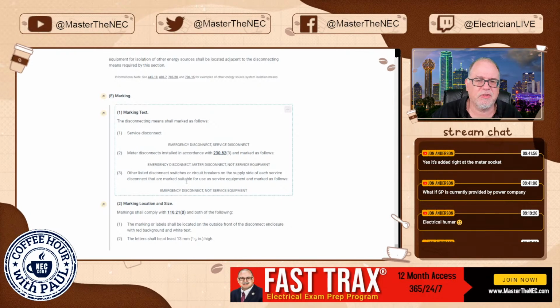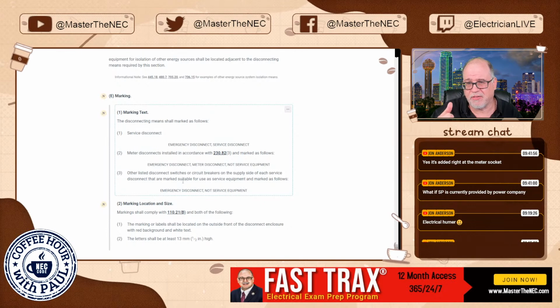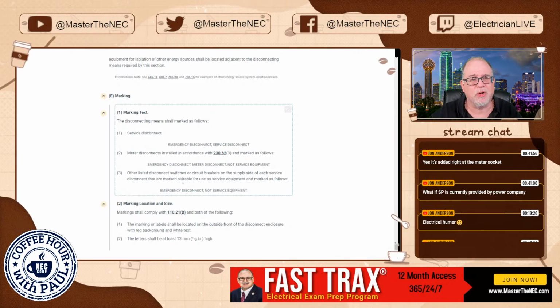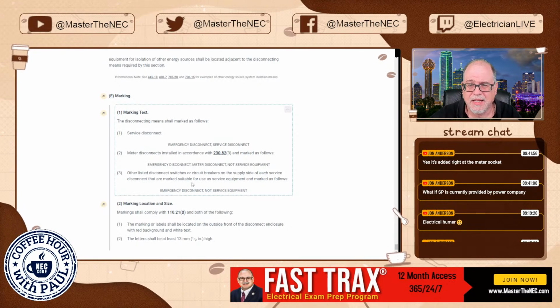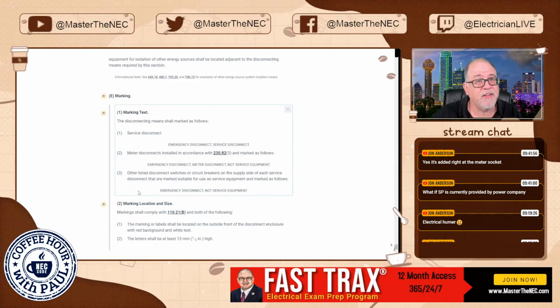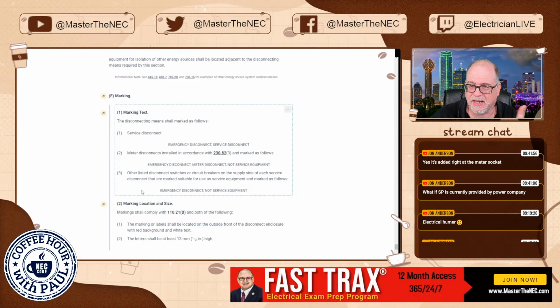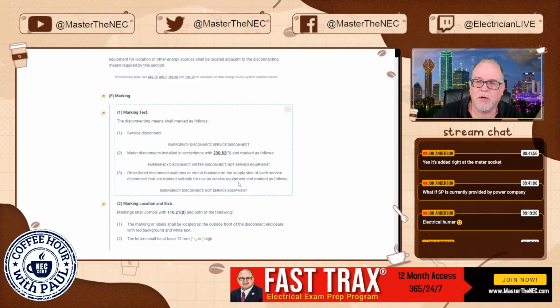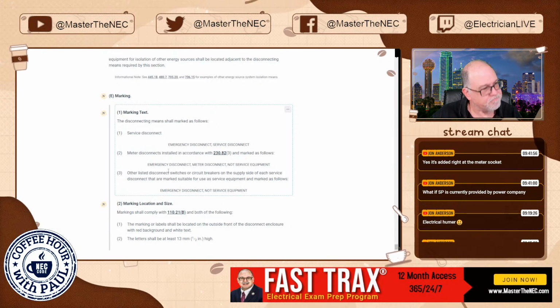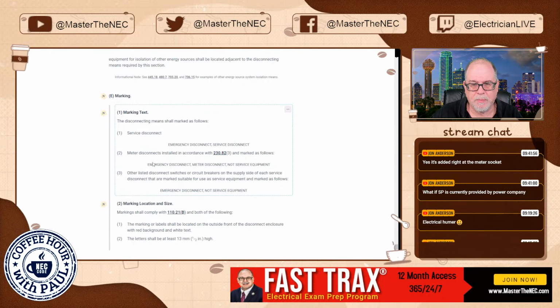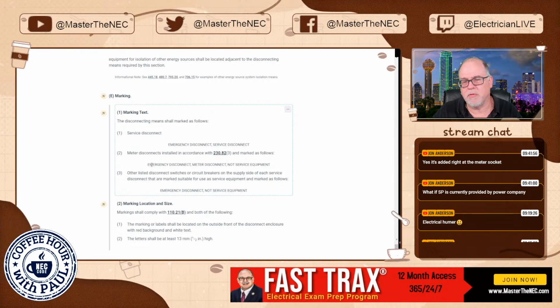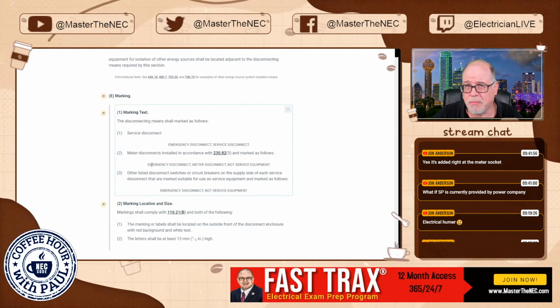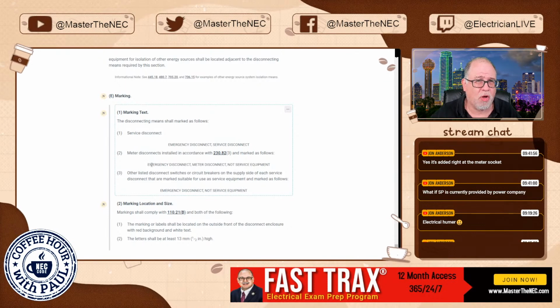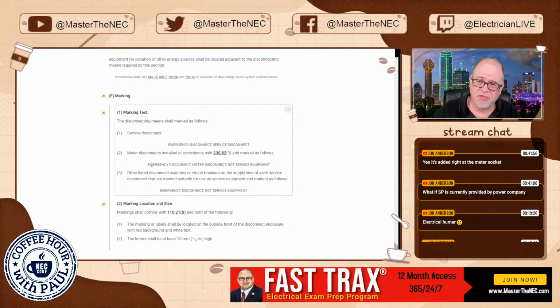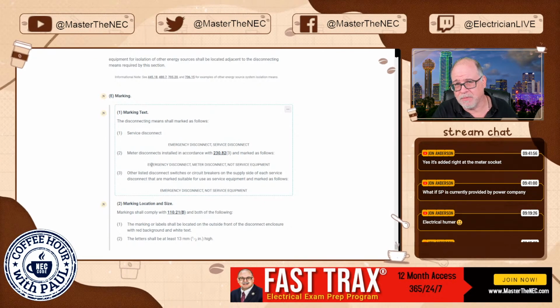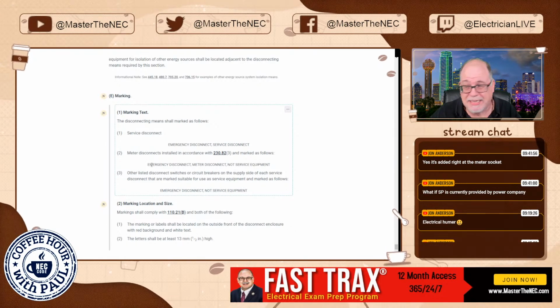And then, of course, number 3 is the classic listed disconnect switch, whether it's a knife switch or circuit breakers. Again, we're using this as a disconnect, and as the emergency disconnect, it is on the supply side of a service disconnect, so that tells you it is not the service disconnect. They are marked suitable for use as service equipment and marked as follows: Emergency disconnect, that's all it is, not service equipment. Why are these things so important? Well, you've got grounding electrode conductors, you've got grounding electrode systems. We have places where we install main bonding jumpers. We have to know what is service equipment and what is not service equipment, okay? And maybe you know this, but somebody coming in later might not, okay?